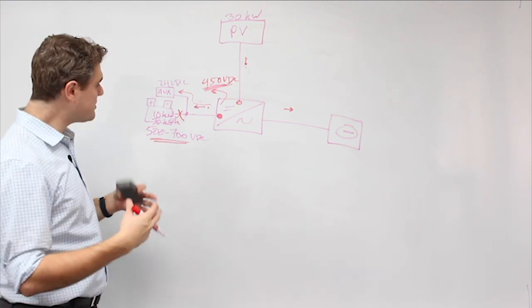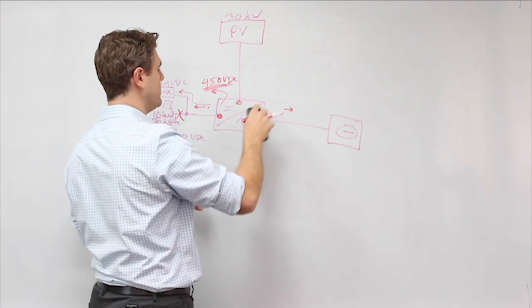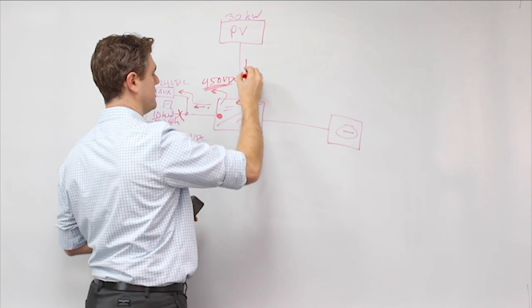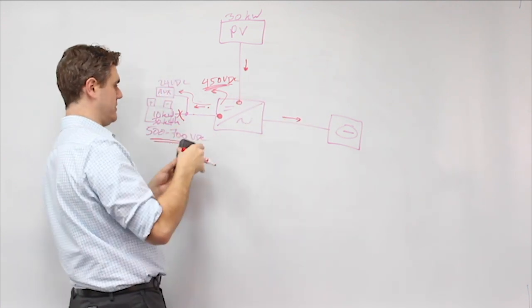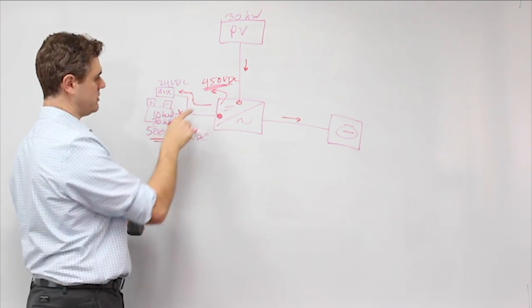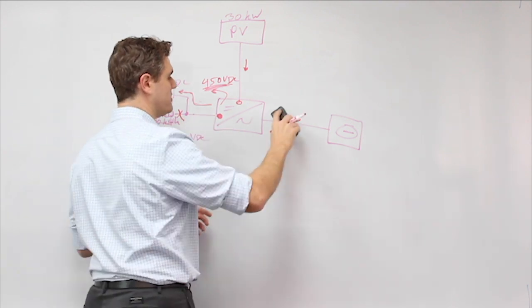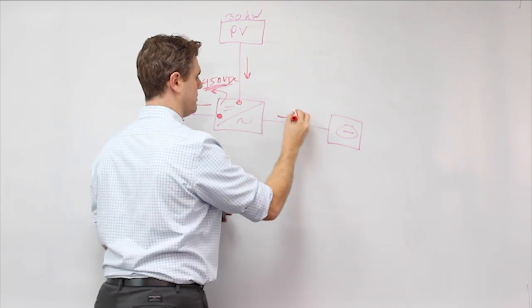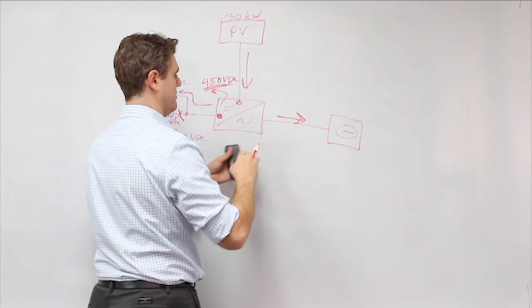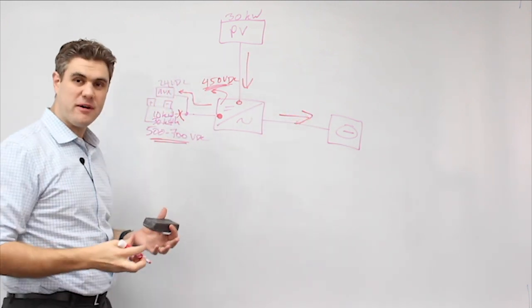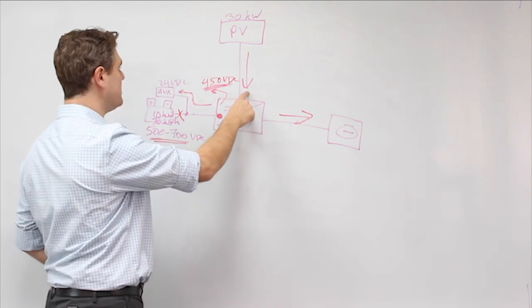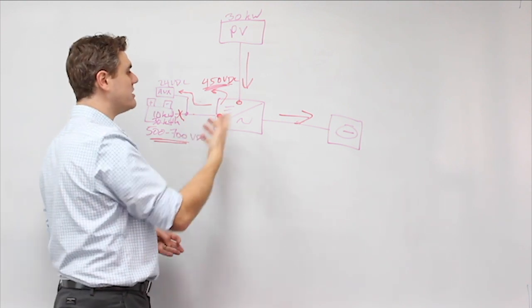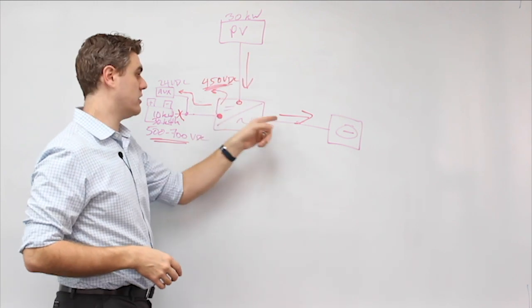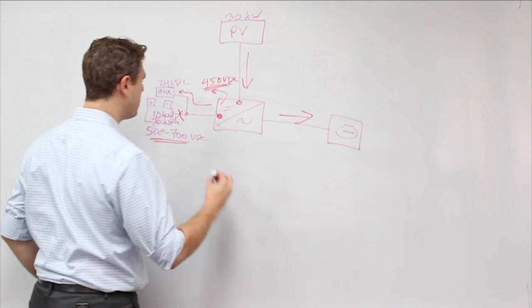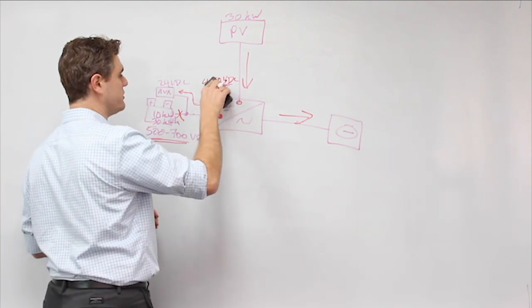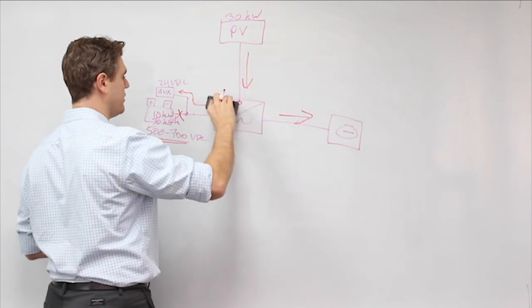Now let's keep going. Let's say the sun starts to rise again. So now this arrow gets a little bigger. We're still off, right? That could still be going, but this is off, 450. But now this arrow gets a little bigger, and the sun rises even more, and even more. And at some point, and again, there's some buffer here, there's some engineering safety factors, but when this arrow is a little bigger than the capacity of this arrow, basically the inverter says, you know what, we can turn the battery back on, and there's plenty of energy here to prevent this from ever flipping around. So at some point it says, this 450 volt limit I just imposed on you, this voltage regulation, I'm eliminating it. You're back to your operating voltage. Everything's hunky-dory.